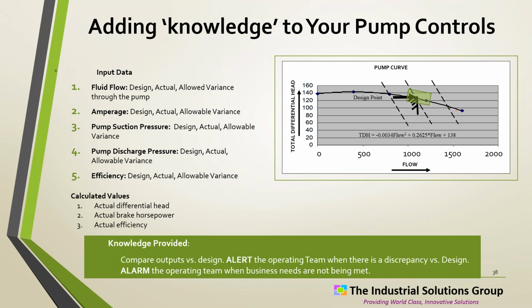So for the input data, we need to know where this system is operating on its curve. And it's easy for us to put together an equation to curve fit a performance curve. What's shown in green here is what's acceptable, the acceptable range. Obviously, you can't be 100% dead on the spot, but if you're within 2%, 5%, pick a range, there's an allowed variance that you can have on this pump. That's all we want to do. We want to know what the design point is, and we want to make sure that we're in that allowable range on things like flow and pressure drop. And we need to check amperage so we can know if we start getting some calibration issues with instruments.